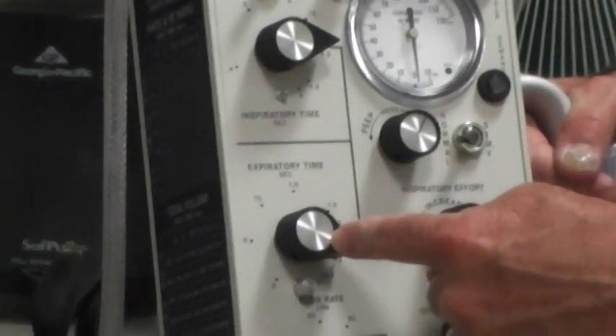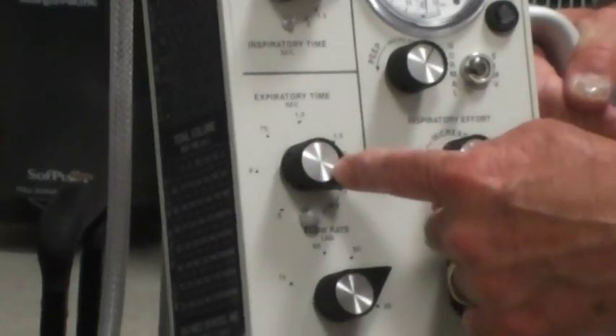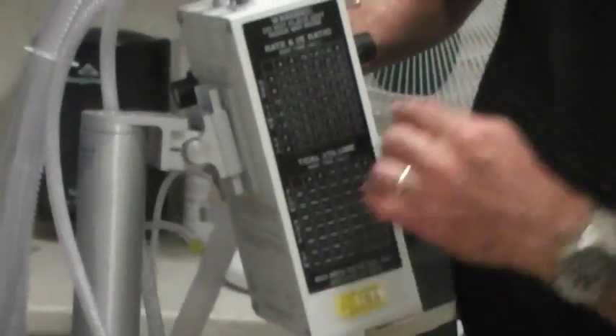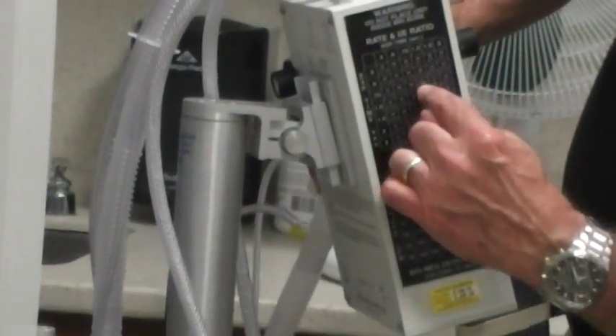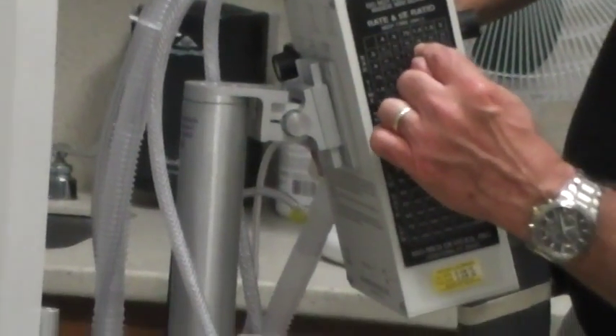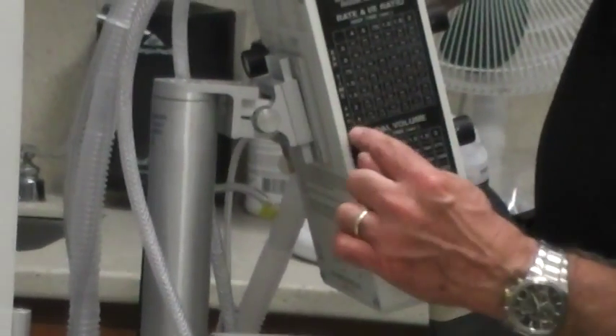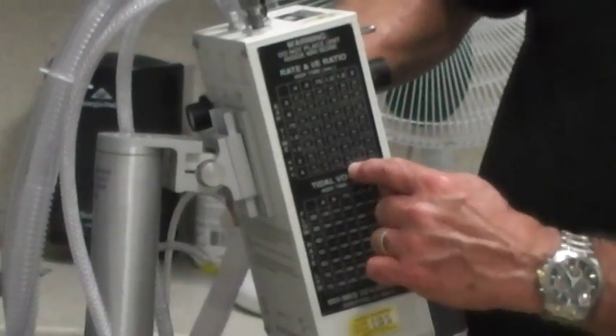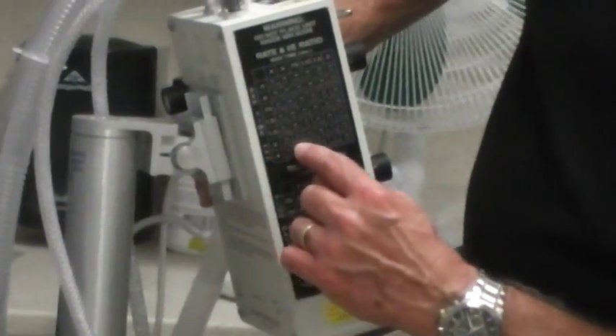The next knob is how we're going to set our rate, but that says expiratory time. It's kind of the old school. I still don't need to know what all that means because I have a little cheat sheet on the side here. So I chose 1 second. If I choose my 1 second column, you see these different rates that are available. If I set my expiratory time at 4, I will get a rate of 12. If I set it at 2, I get a rate of 20.